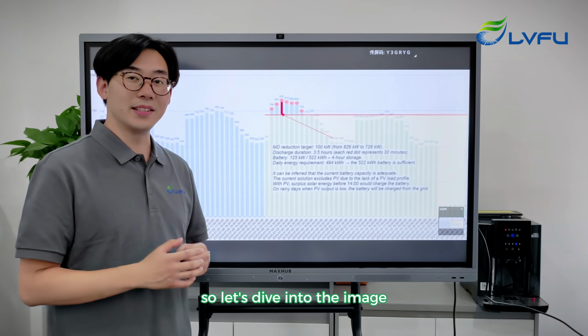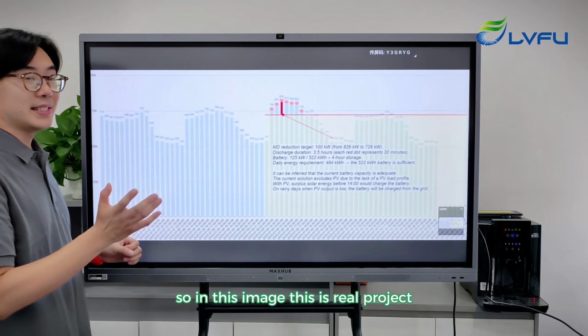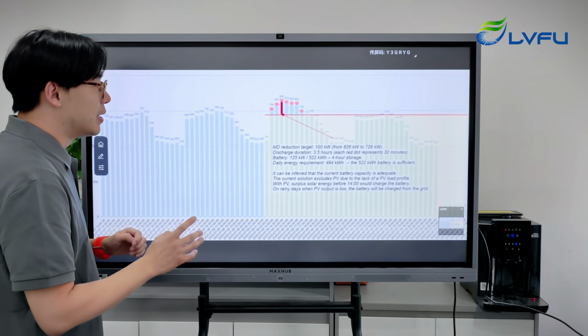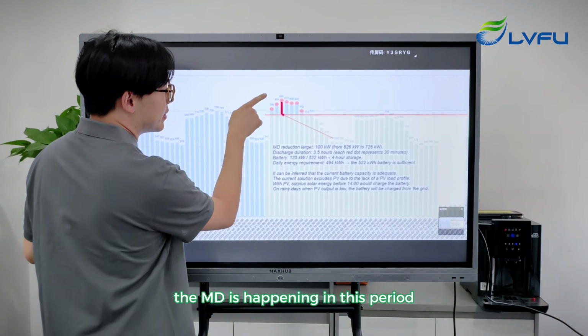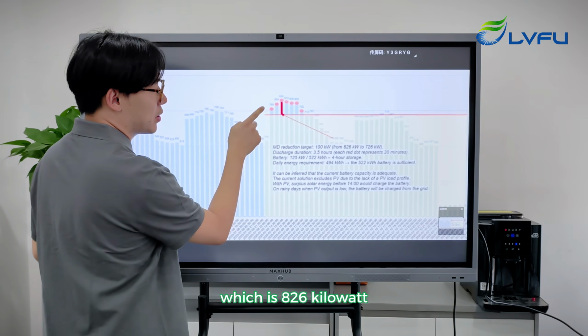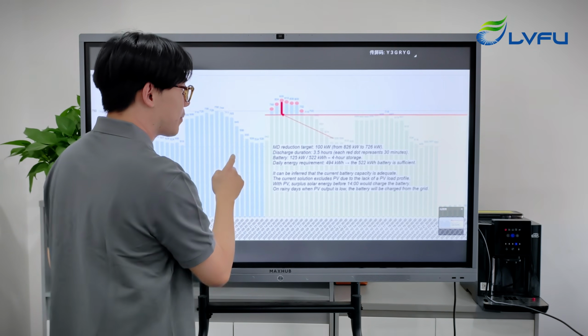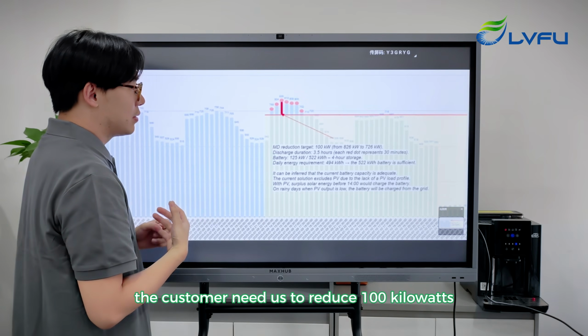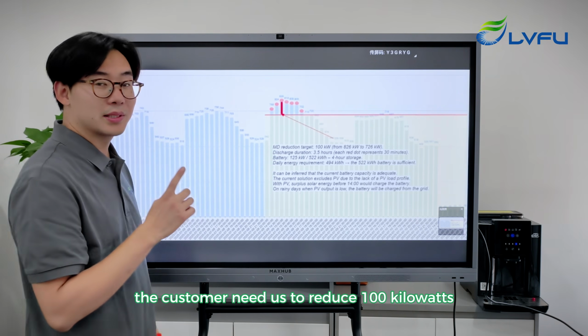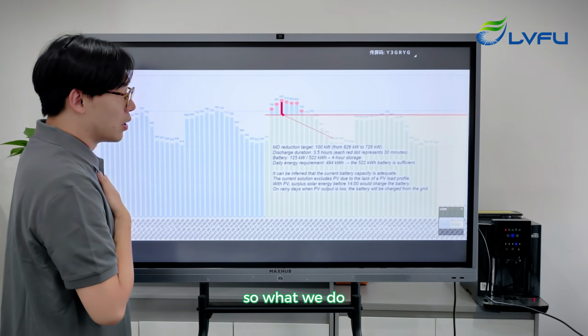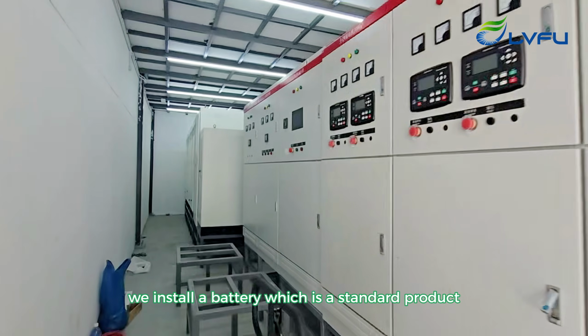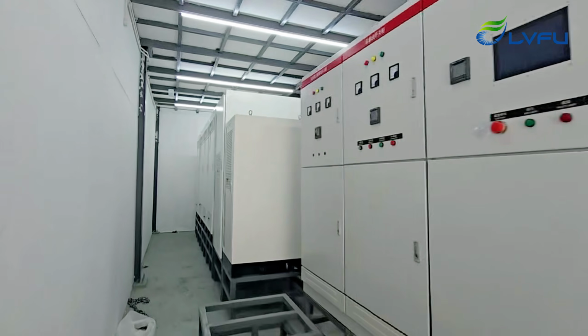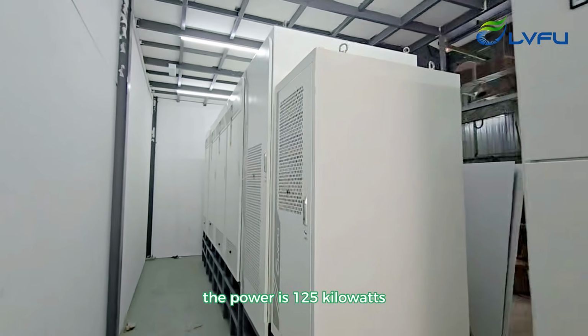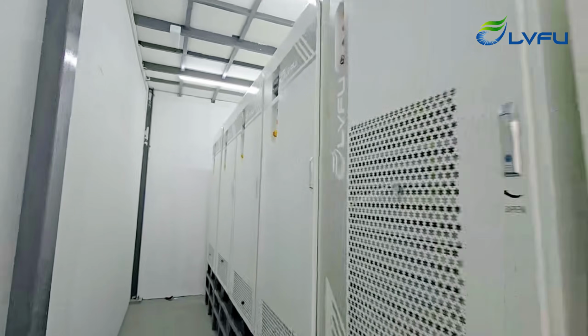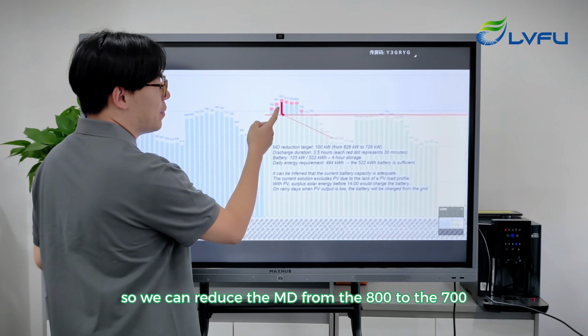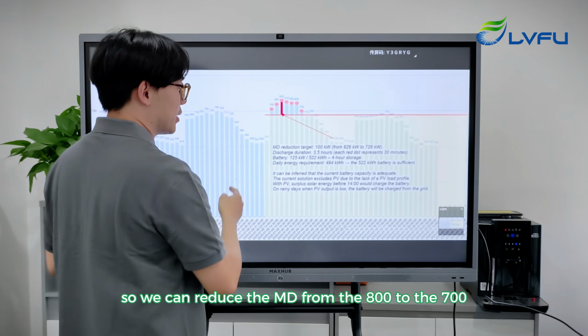So let's dive into the image. This is a real project. The MD happens in this period, which is 826 kilowatts. The customer needs us to reduce 100 kilowatts. So what do we do? We install a battery, which is a standard product. The power is 125 kilowatts. So we can reduce the MD from 800 to 700.